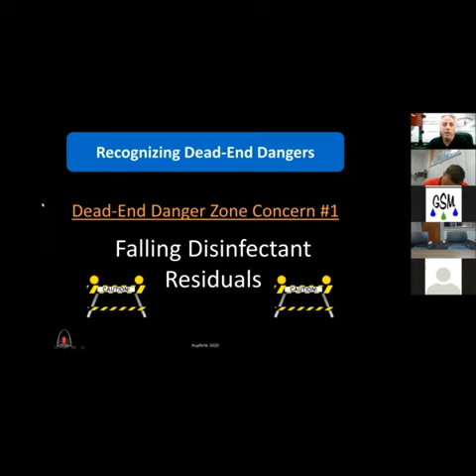If you look at the chart here, chlorine disinfection dissipates as water ages. A minimum of 0.2 ppm is required as a residual for most states. Most states are at a 0.2, some are higher, 0.4 for Florida. Parts of Louisiana are actually at a 1.0. They've had a battle with a brain-eating amoeba infiltration in several of the parish water systems down in Louisiana, so they've been at a 1.0 for a while.